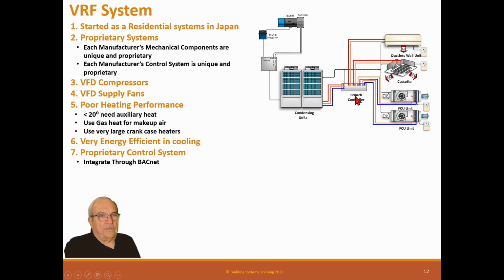I did a large one for the government, and the engineer had a little black box on the drawing, and I said, well, how am I supposed to control this system? And he said, well, the salesman for the VRF systems guaranteed me this system will integrate seamlessly to your control system. I said, okay, so I've got to figure this out. So I went and figured it out, and what happens is they allow a BACnet integrator into the system that allows us to get onto it and be able to see it.